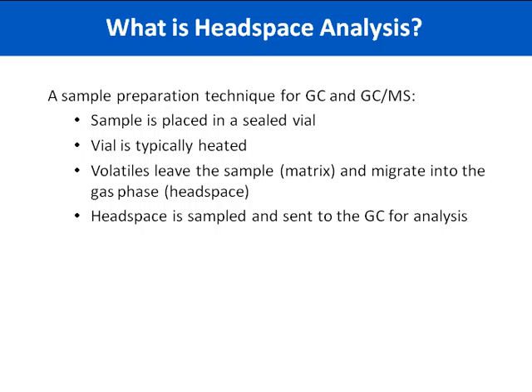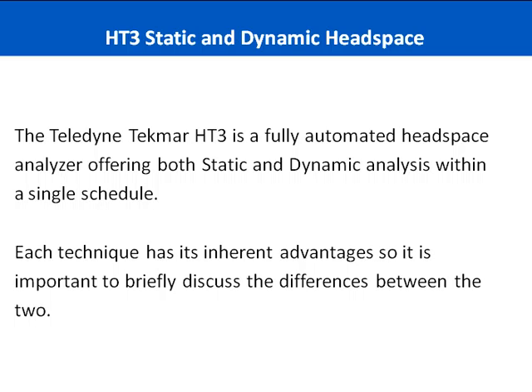Generally speaking, for headspace analysis, the sample is placed in a glass vial, which is sealed with a Teflon-based septum. The gas above the sample, which is typically air, is called the headspace. That sealed vial is then heated to a temperature appropriate for both the matrix and the analyte. The volatiles in that sample are then going to leave the sample and migrate into the headspace above it. This headspace is sampled by placing a needle into that vial, which is pressurized. This allows the sample to fill a fixed volume loop if you're using the static technique, or to continuously be swept onto an analytical trap if you're using the dynamic technique.